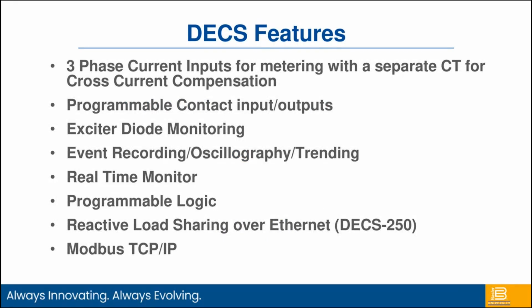Other DECS features: the DECS is able to sense three-phase current, where traditionally it's been single-phase current, and we also have a separate CT for cross-current compensation. That's to make sure that we're still able to meter. The idea is that all the currents within all the CTs across machines will balance each other out and don't allow for proper metering, which also affects protection such as limiters and other things. So we can get three-phase current inputs. We have programmable I/O to do whatever functions we need it to do.